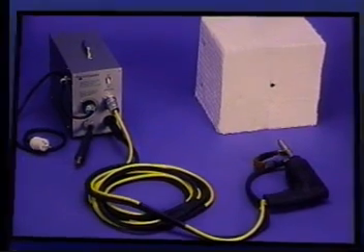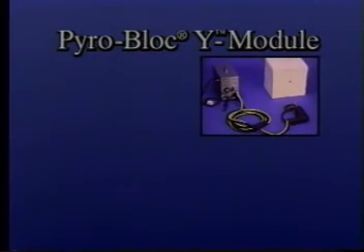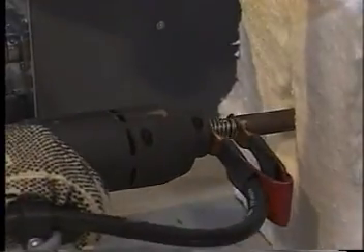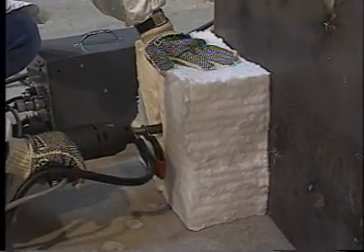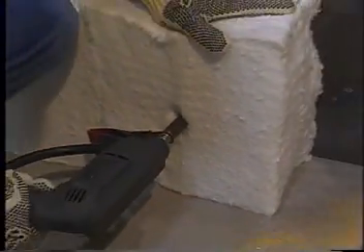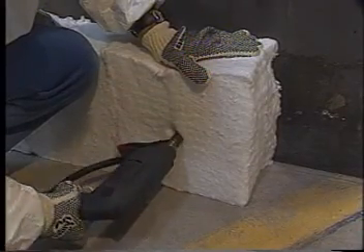As the backbone of the Pyro-Bloc line of weld-on modules, the Y module is the industry standard, making it the module of choice for non-coated casings due to its consistency, reliability, ease and speed of installation, and its long service life. Installation is fast, easy, and reliable using the industry standard Pyro-Bloc stud guns. No pre-layout of studs is necessary. The Y module features the original center mount stud system that allows for convenient one-step welding and module attachment by merely inserting the Pyro-Bloc stud gun and pulling the trigger.